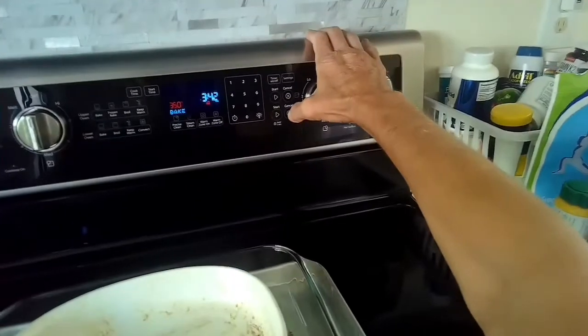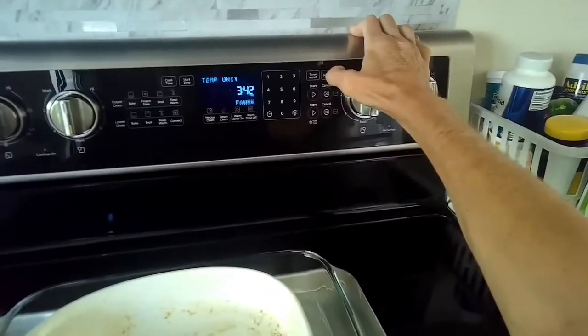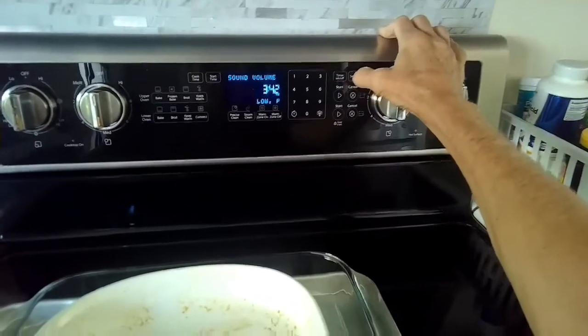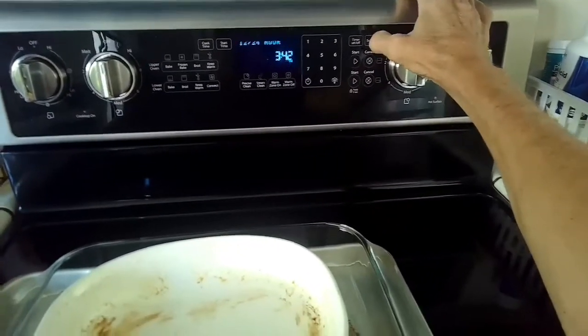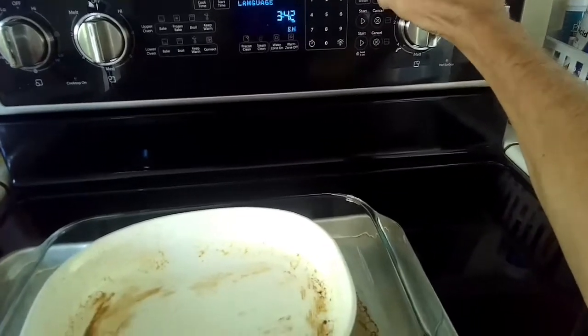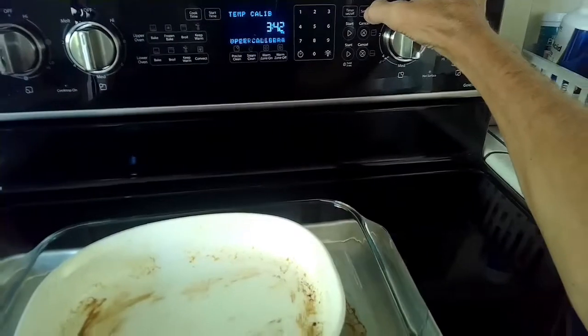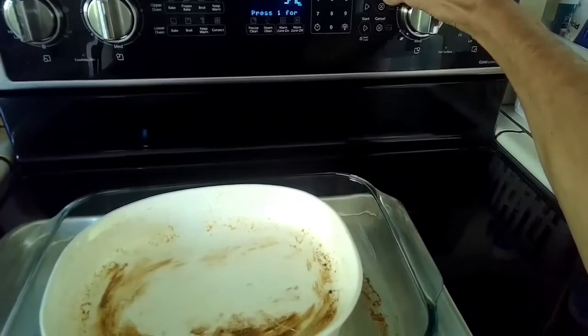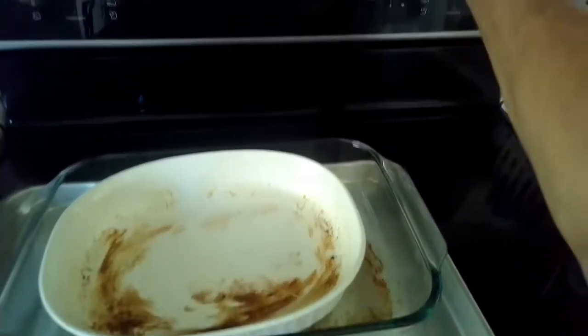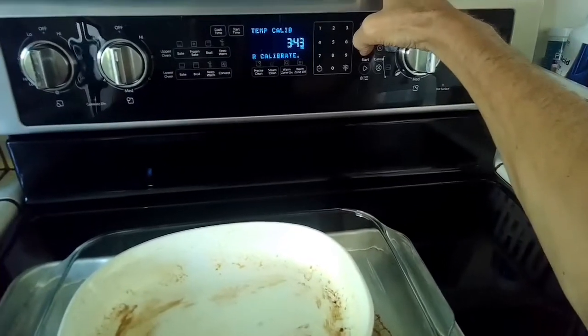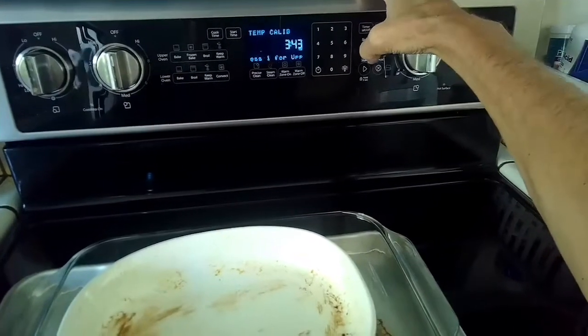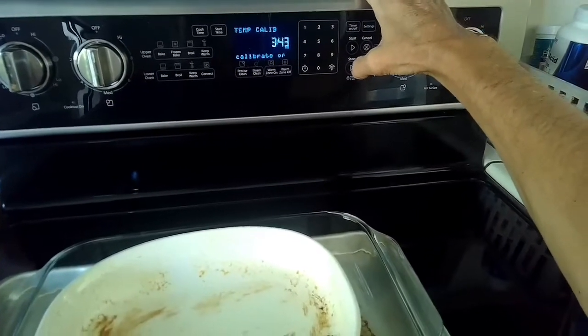That's cool. That one looks like it's just a tiny bit above 350. Probably 5 degrees. I'm going to see if I can go down by 5 degrees to really hit that calibration right. So I'll cancel, go settings, and keep pressing it until I get to temperature calibration, which again I think is about 12 clicks in. So press 1 for lower. Okay, let's do that. Lower selected.